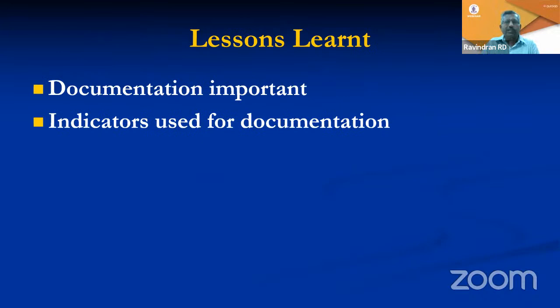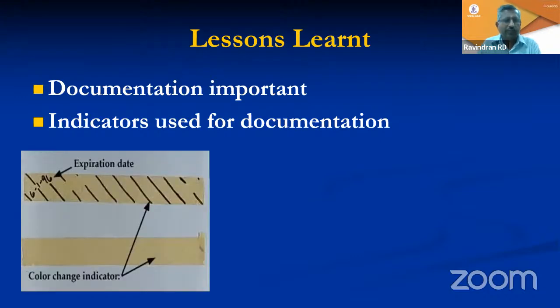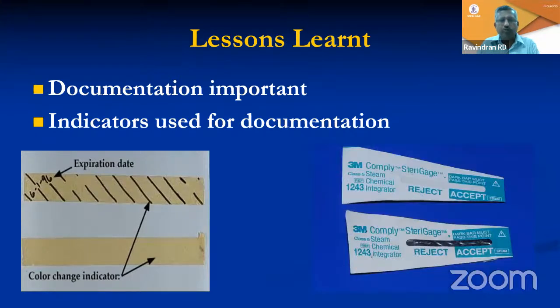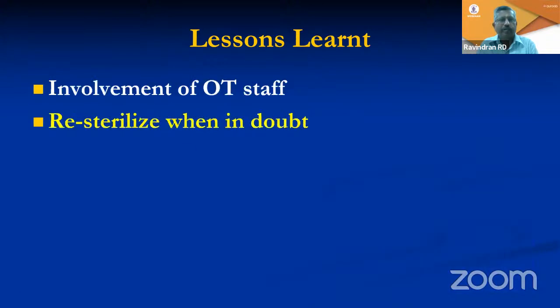So what is the lesson we learned from it? The documentation is very important. The indicator we use for documentation is very important. We were using class 1 indicators. With this class 1 indicator, even a minimal change in temperature can change the indicator tape, and it does not indicate the pressure. So there was a time we also switched over to class 5 indicators, where you need both the temperature at a certain level and also the pressure. As a result of this incident, we switched over to this, and whether it is a long cycle or a short cycle, this indicator is used for every load or every bin. So this is one important lesson we learned.